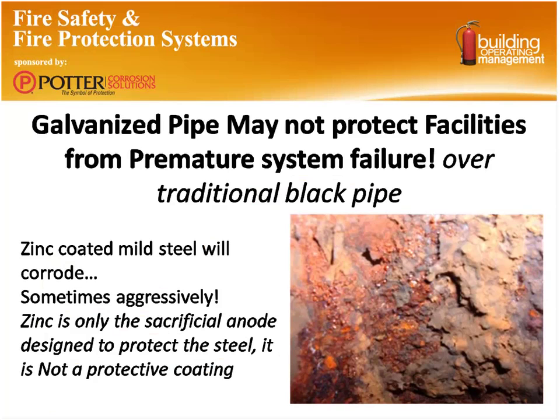So you say, well, I've got galvanized pipe. Galvanizing protects my pipe. Well, that is true. It does help slow the process. If you think about galvanizing, the reality is zinc is considered a sacrificial anode, and what it's there to do is slow the galvanic action and give that pipe some protection.